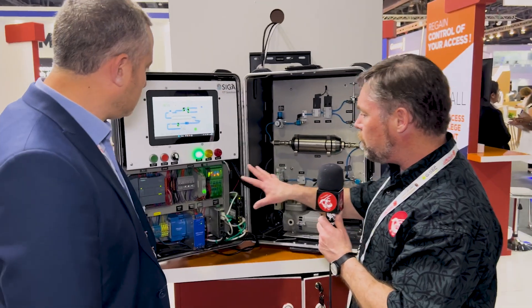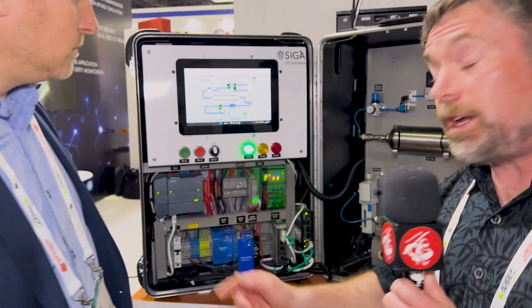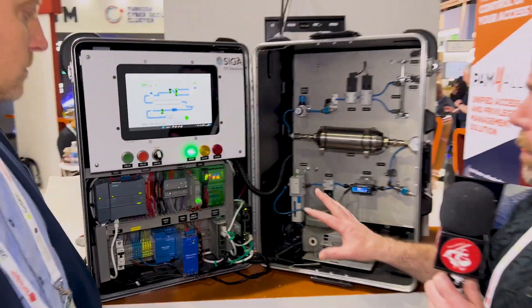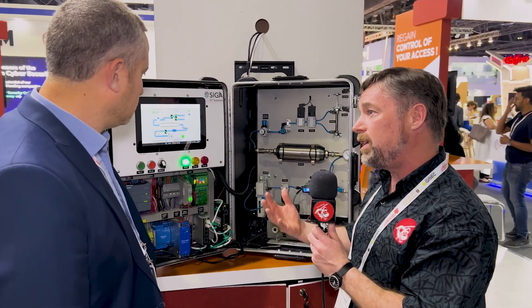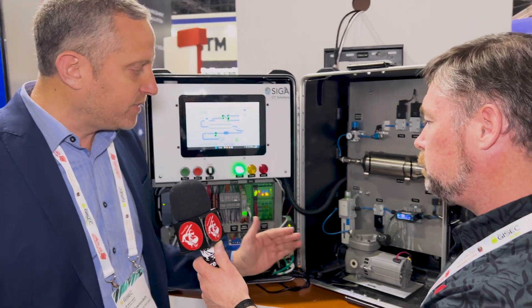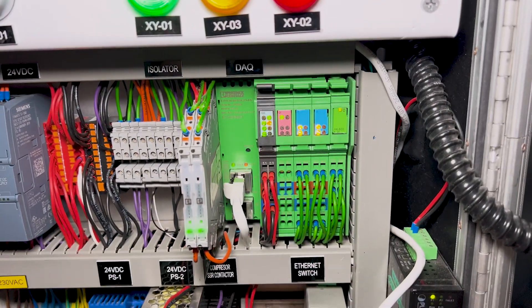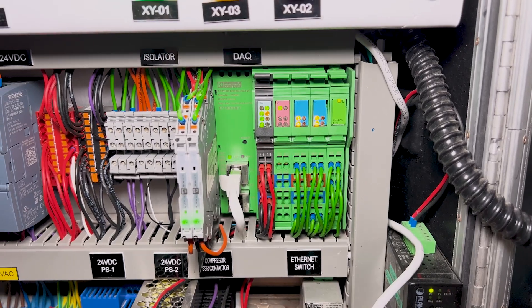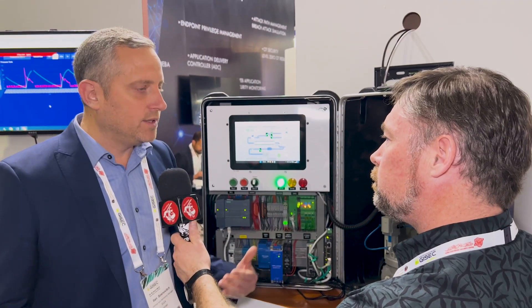I see you have the physical — there are sensors here, and your system intercepts the sensor data and takes a copy of it. One copy goes to the Siemens, and here we see the Siemens S7 SCADA language that we're familiar with. Other SCADA languages would be DNP3 and languages like that. And then your system has a type of machine learning that sees the normal behavior of the industrial system — is that correct? Exactly. We intercept the signal coming from the sensors to the PLC while they're still analog electrical signals, before they're digitized, and that helps us to be out of band. We take those signals safely and unidirectionally into our platform, where we analyze the performance of the sensors, the machines, and the process to make sure they're running according to their normal behavior and not misbehaving due to any cyber attack.